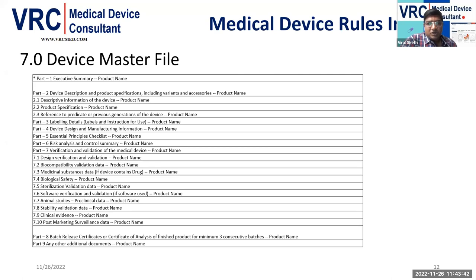There are almost 11 to 12 types of biocompatibility tests being done in vivo or in vitro, meaning in a laboratory or with animals. For that, we should follow the ISO 10993 part 1 standards, where we need to identify the minimum tests required to comply, depending on the class of the device and how it interacts or comes in contact with the body. There is a specific table given in those standards that we should understand when we refer to them.